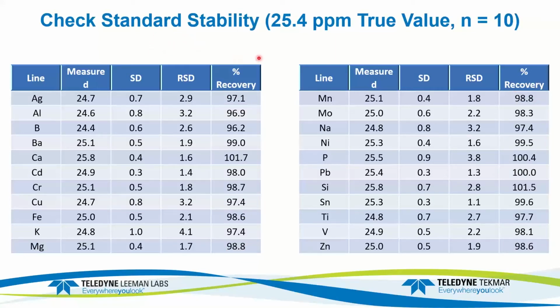We ran this 25 ppm check standard every 12 samples. And we can see the overall recovery again is very, very close to the theoretical value. Even though we were running different samples, there was no drift, and also there were no updates. We did no optics update during the run. There's no slope or intercept updates of the calibration curve, and no internal standard. So the instrument shows really quite good stability.